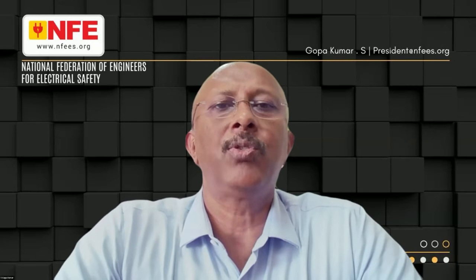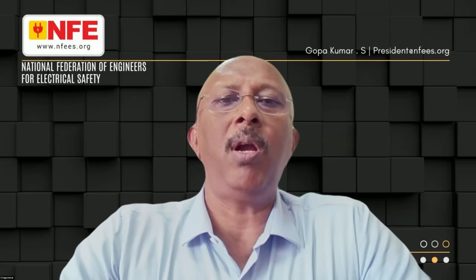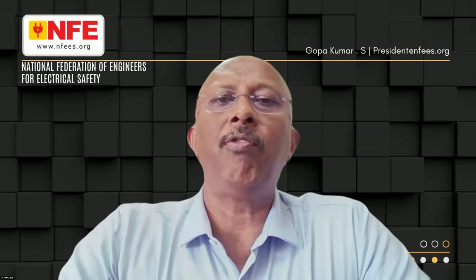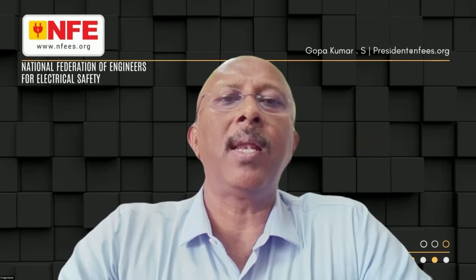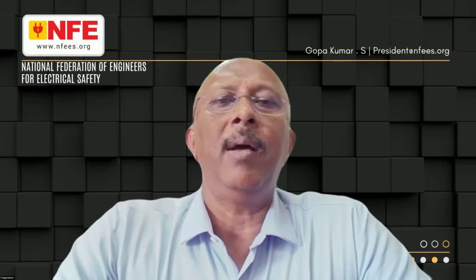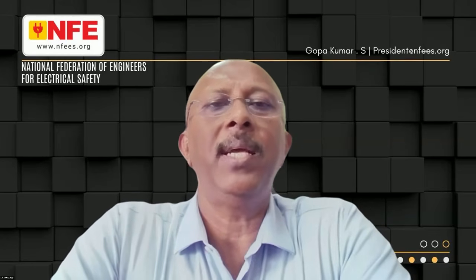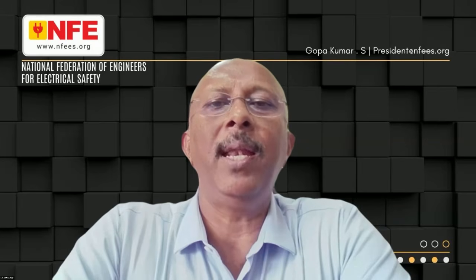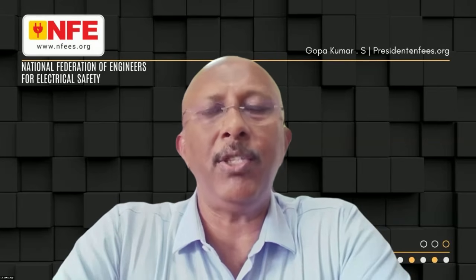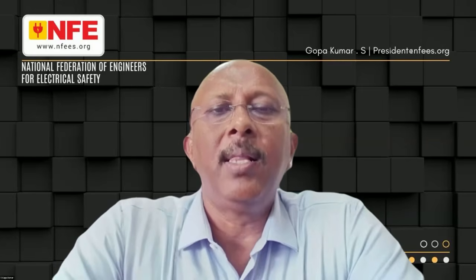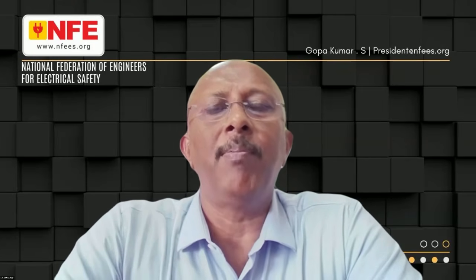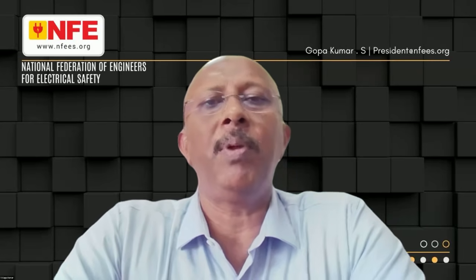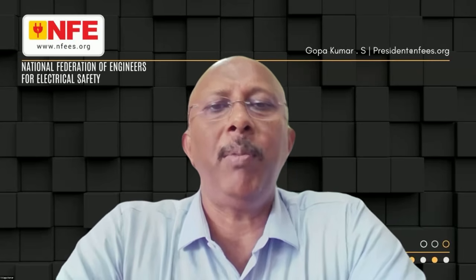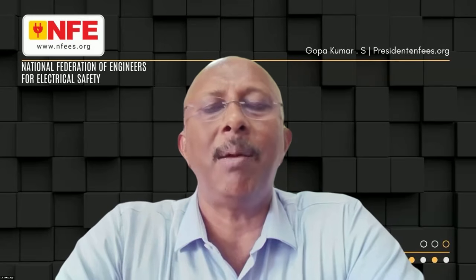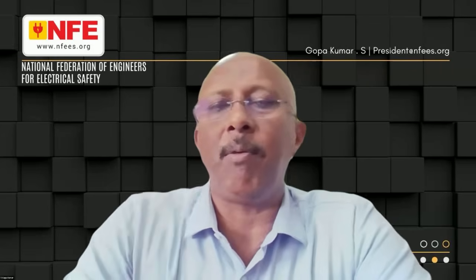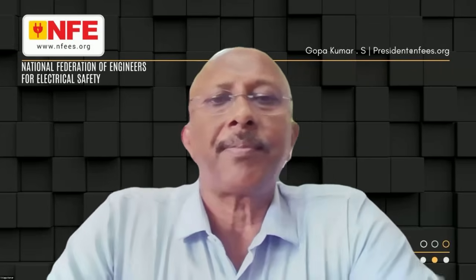So the next question: it is a fault of the display of the ventilator only, so no fault in electrical wiring. Mr. Upadhyay is saying probably in the video, it is the fault of the ventilator which was creating fire. It is not like that. The equipment will safely work, provided the supply is supporting the equipment properly.